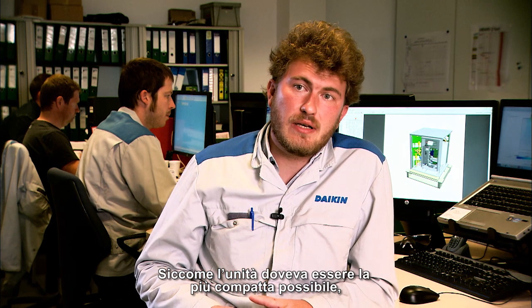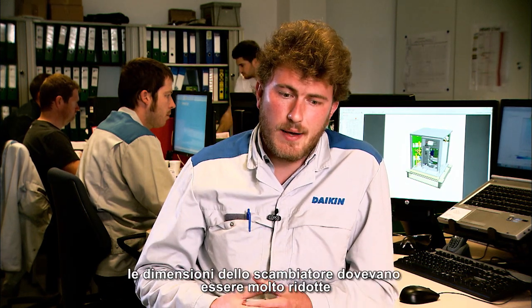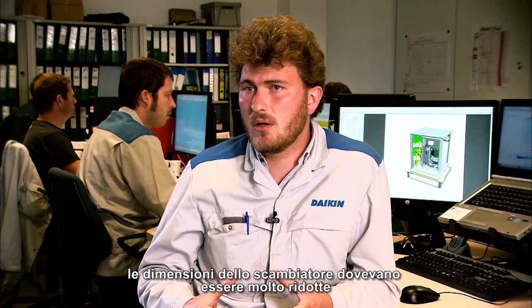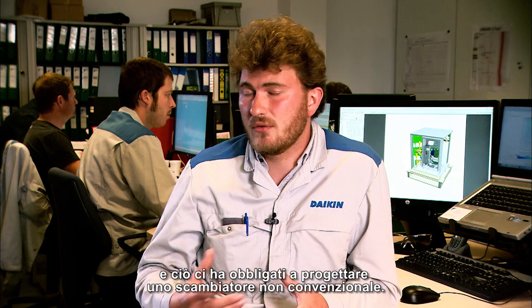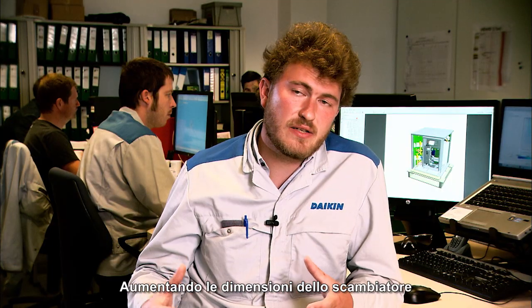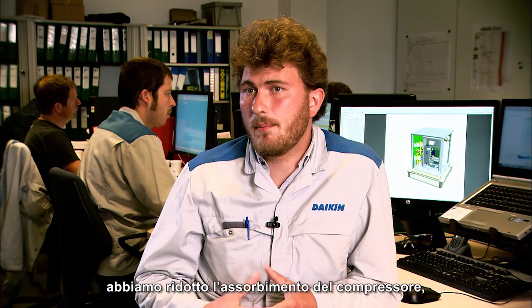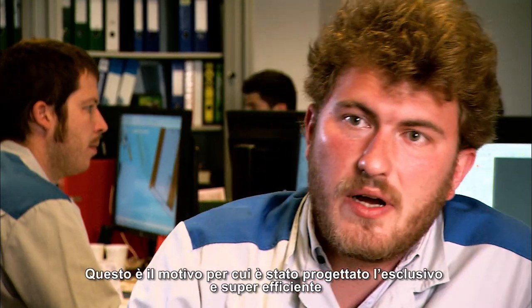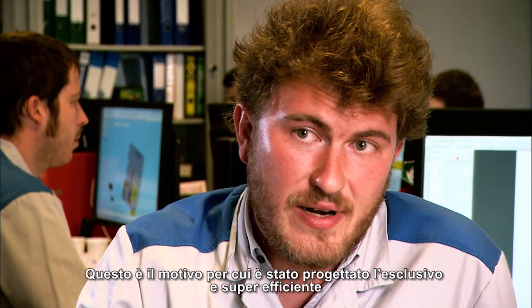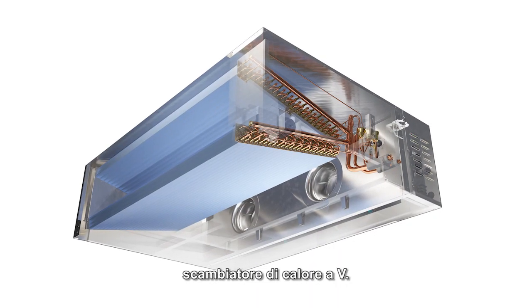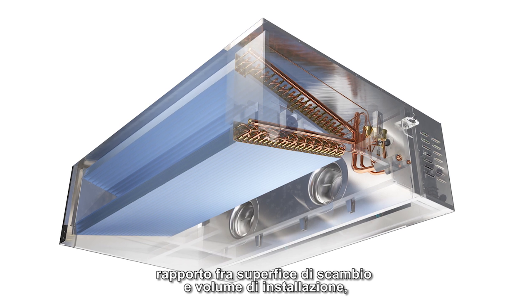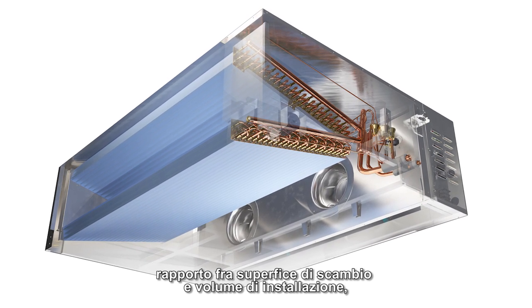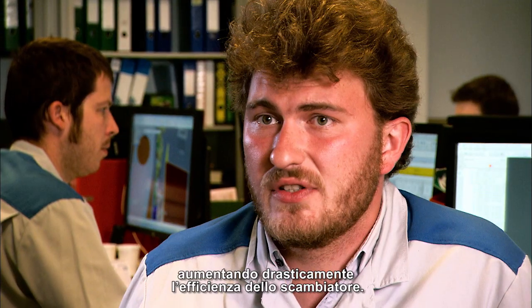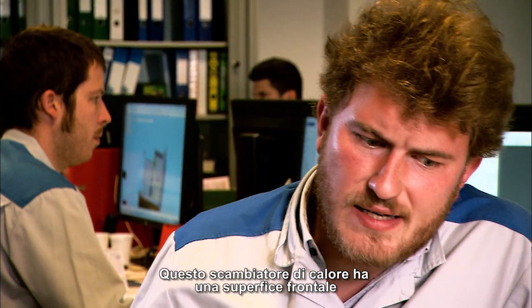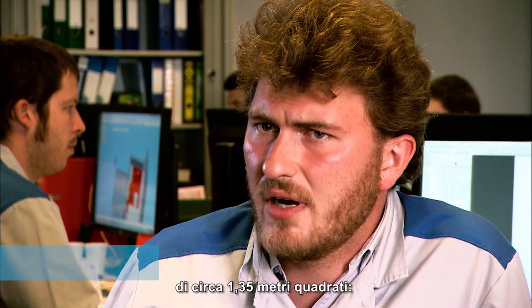Because the unit needed to be as compact as possible, our heat exchanger would be very small if we limited ourselves to the conventional heat exchanger design. When we increase the size of a heat exchanger, we reduce the power input to the compressor due to lower demanding refrigerant temperatures. This is why we designed this very unique and very efficient V-shaped heat exchanger. This heat exchanger has a very high heat exchanging surface to installation volume ratio, thus drastically improving its efficiency. It has a frontal surface of about 1.35 square meters.